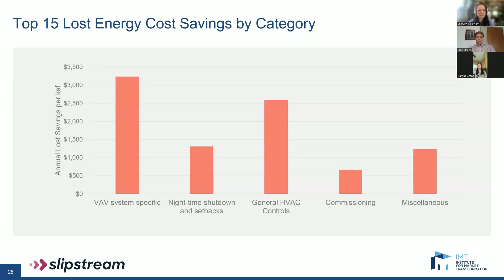So now we can take a closer look at each of those measures within each category, starting off with the complex measures in the VAV systems. The first one here, VAV ventilation optimization, is the highest measure for loss savings per square foot. This measure did not appear to be implemented in any of the projects that we've seen so far. And it's not surprising because this measure has proven to be a pretty complex code element that many design engineers, contractors, and facility managers do not fully understand or just confuse with demand control ventilation. So this is a good example of an element that needs additional training in both the design and controls community.